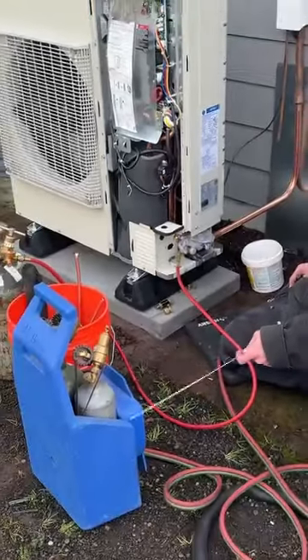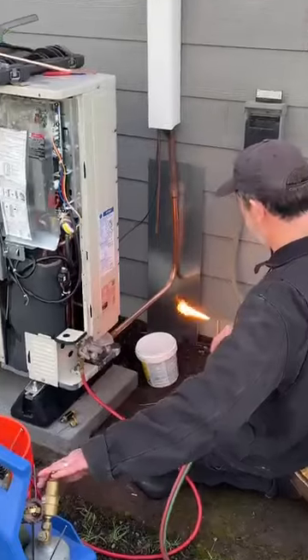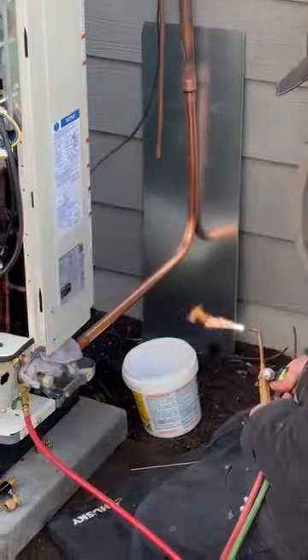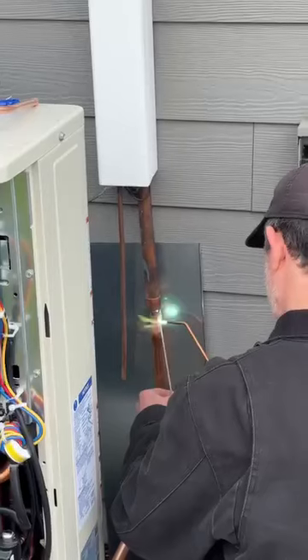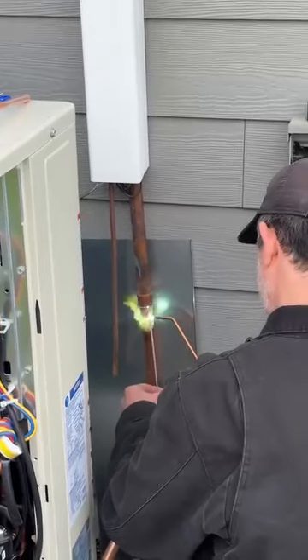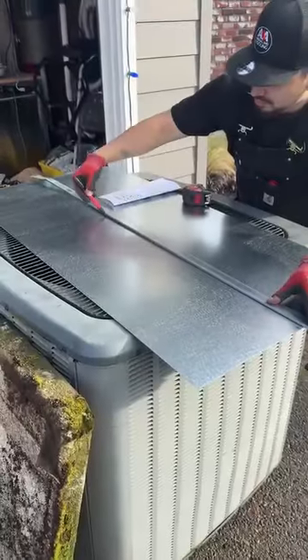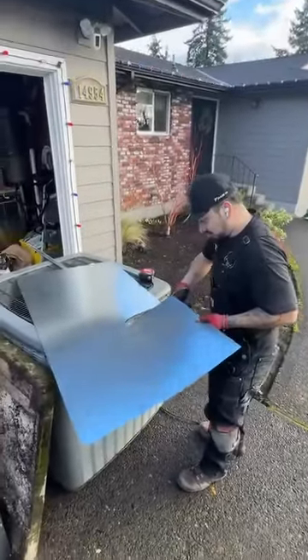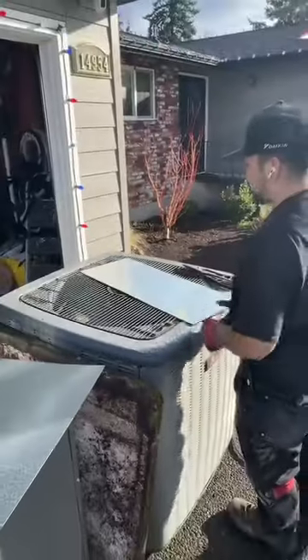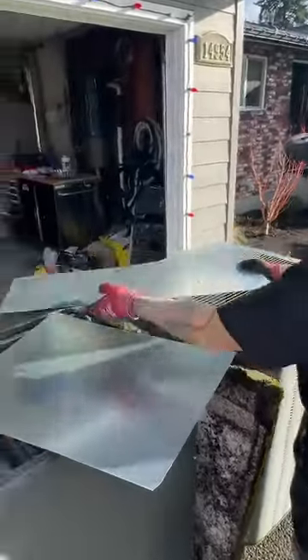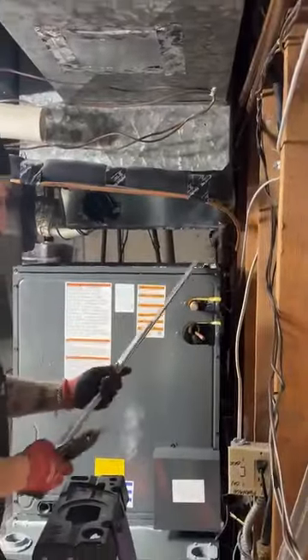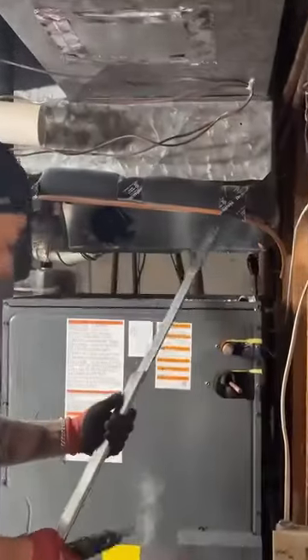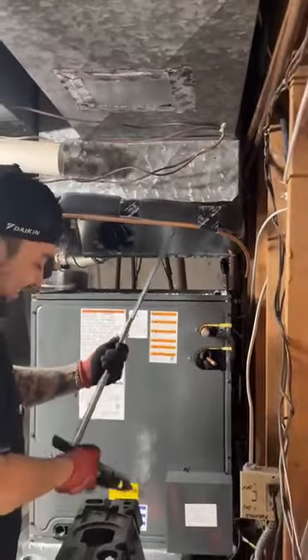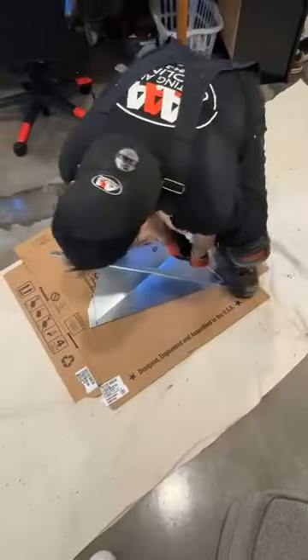After clearing out the lines with nitrogen, it's time to begin the brazing process for the outdoor unit, welding the lines to the unit which provides flow of refrigerant within those lines. Simultaneously, we begin measuring and cutting sheet metal outside to build that transition ductwork for the indoor furnace and the coil setup. Same step here as we did earlier, we install a metal framing around the unit so we can slide the metal in and have it securely held. We add cross braces to prevent wobble.